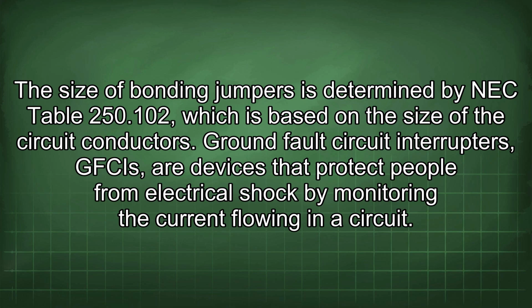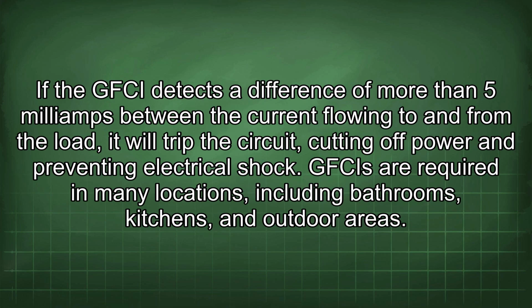Ground fault circuit interrupters, GFCIs, are devices that protect people from electrical shock by monitoring the current flowing in a circuit. If the GFCI detects a difference of more than 5 mA between the current flowing to and from a load, it will trip the circuit, cutting off power and preventing electrical shock. GFCIs are required in many locations, including bathrooms, kitchens, and outdoor areas.